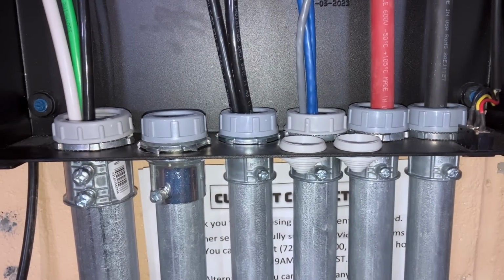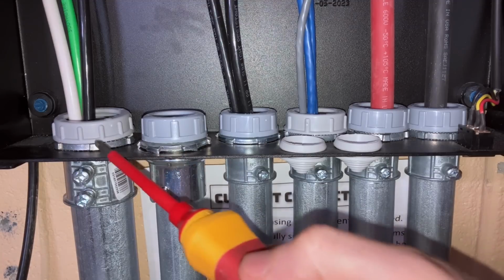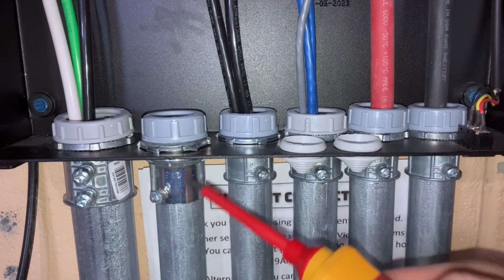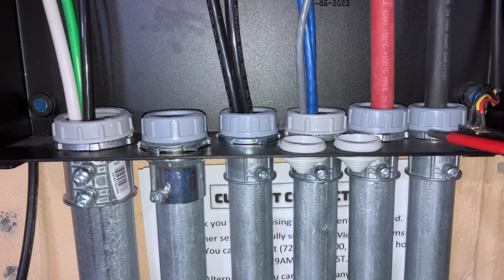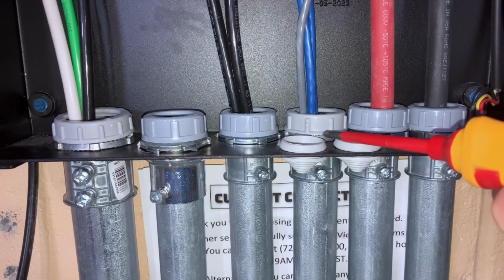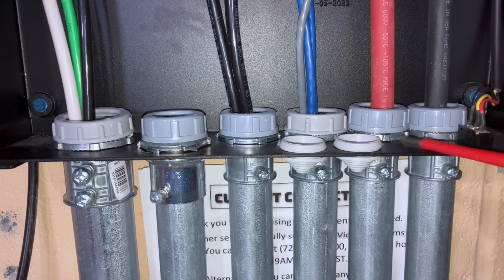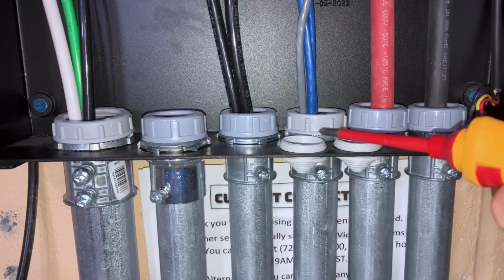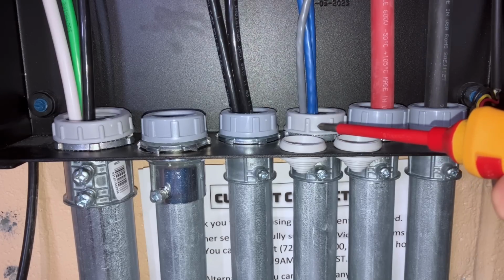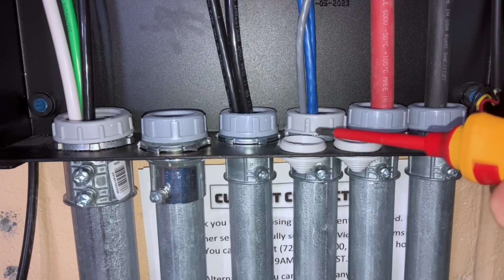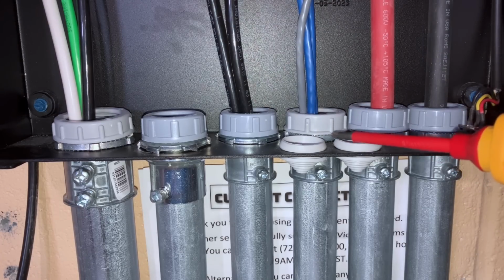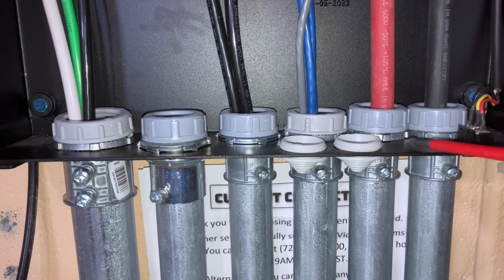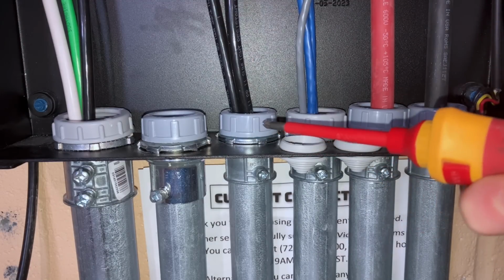Now while we've got this opened up, one thing that I did not care for too much about this specific inverter is they are not really designed to have these conduits. The spacing is very tight. In fact, in order for me to get these conduit fittings in here, I actually had to shave down the threads on these so they would fit through the existing holes in the bottom plate of the inverter.